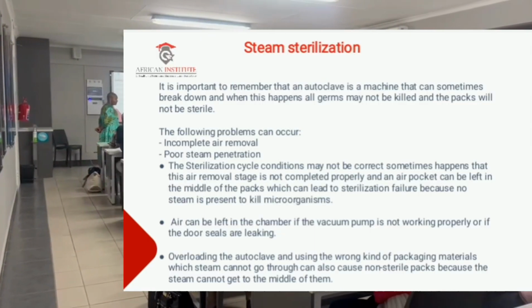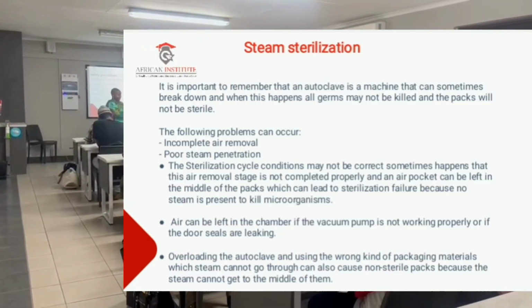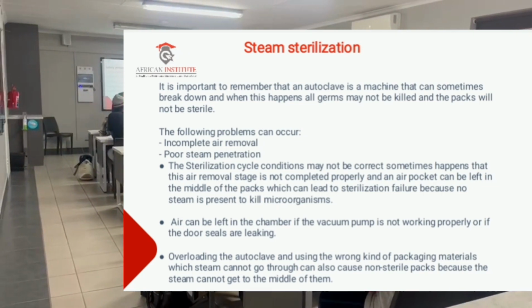Air can be left in the chamber if the vacuum pump is not working properly or if the door seal is leaking. Overloading the autoclave and using the wrong kind of packaging material, which steam cannot go through, can also cause non-sterile packs because the steam cannot get into the middle of them.